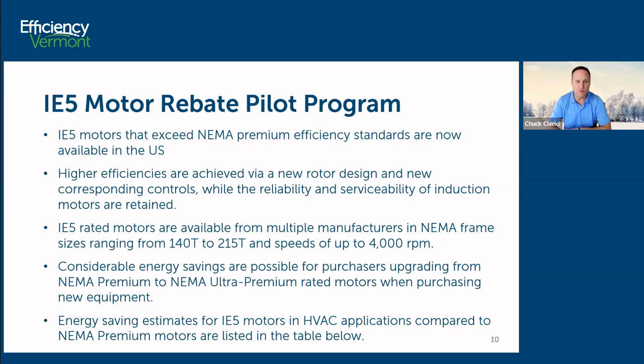The purpose of this program is more the retrofit and replacement market. The higher efficiencies for these new motors are achieved via new rotor design and corresponding controls, while also maintaining the reliability and serviceability of the induction motor. They're made in multiple NEMA frame sizes from 140T to 215T and speeds up to 4,000 RPM. I will say I've seen a couple of 20 horsepower HVAC motors out in the marketplace in the 250 frame size, and the corresponding IE5 motor is in the 215 or 210 class. That's going to be a little bit of a mismatch in terms of shaft position.